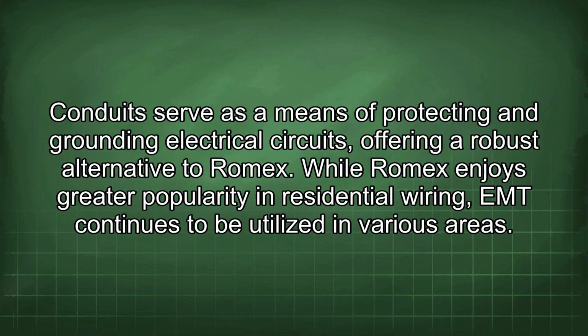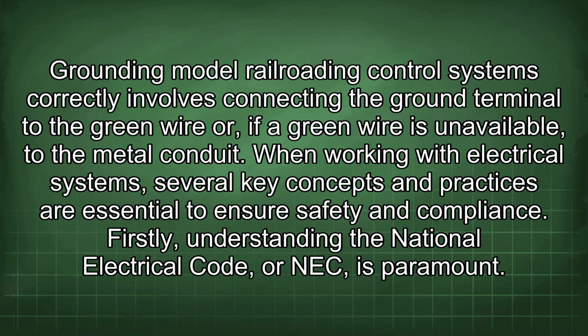Conduits serve as a means of protecting and grounding electrical circuits, offering a robust alternative to Romex. While Romex enjoys greater popularity in residential wiring, EMT continues to be utilized in various areas. Grounding model railroading control systems correctly involves connecting the ground terminal to the green wire or, if a green wire is unavailable, to the metal conduit.